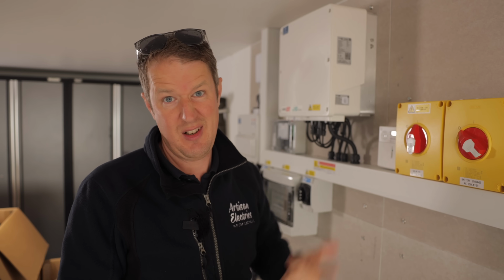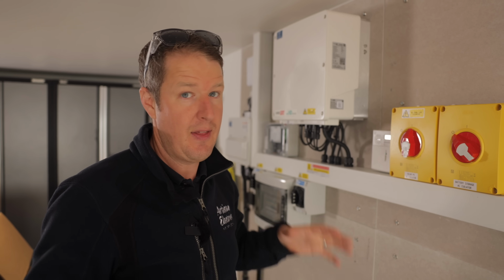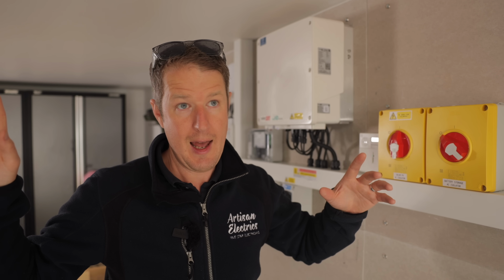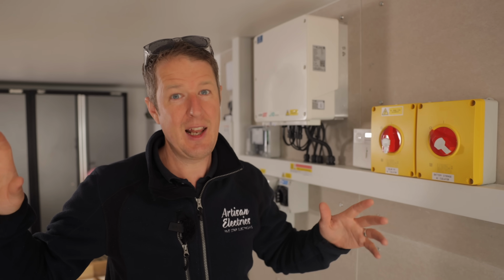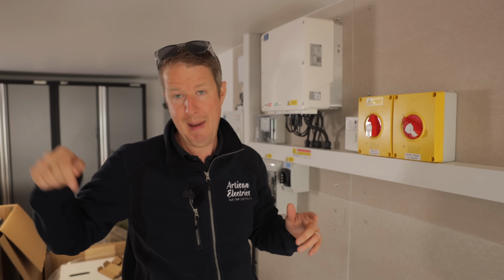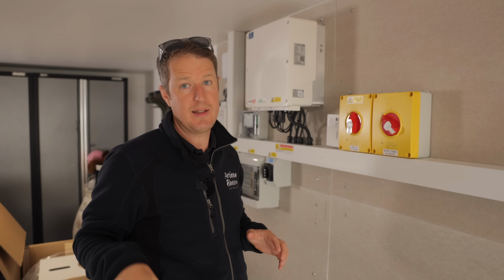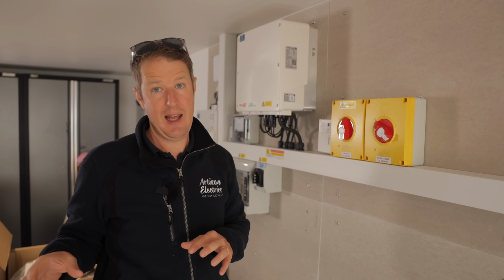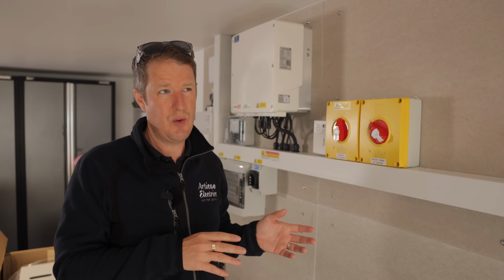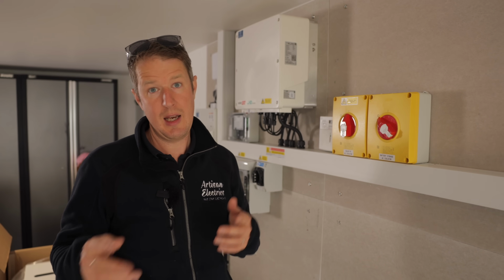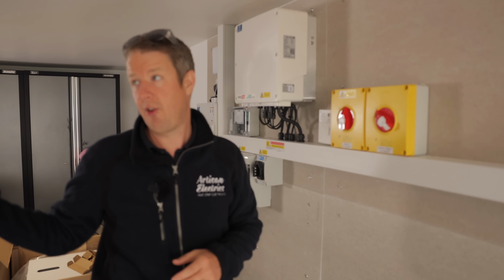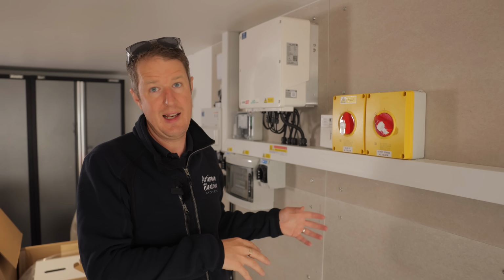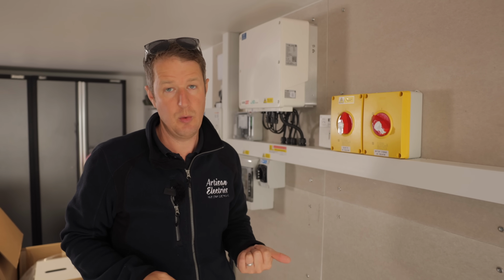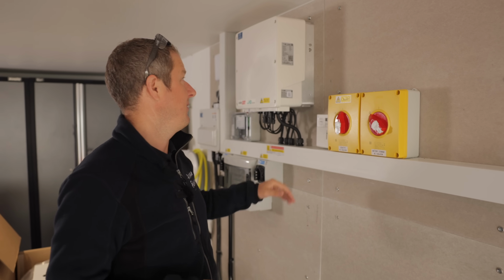Surely that would save money and be more efficient because you can take the DC straight into the Libbi. The thing is that we've got 32 panels on this roof, over 10 kilowatts of panels, and the maximum amount of solar panels that you can connect to the Libbi inverter is about 6 kilowatts, 3.25 kilowatts per string, and you can have 2 strings. So we would never have been able to connect all of these into the Libbi, which would mean that we'd have to either fit fewer panels or use an alternative system, which is what we've done.